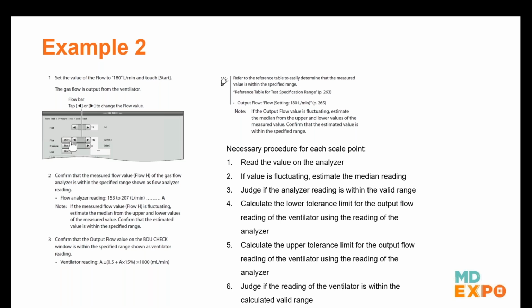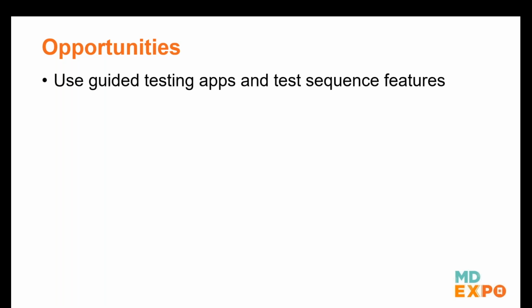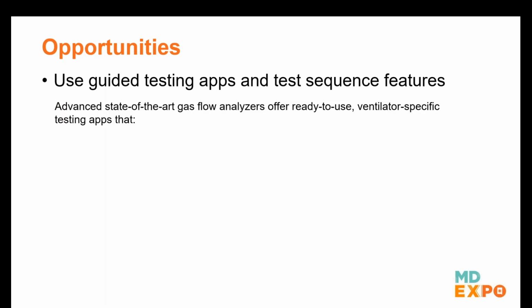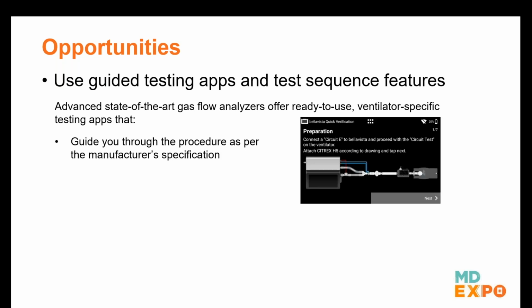So the last opportunity I want to talk about here is actually a feature that the latest gas flow analyzers on the market offer that not only resolves this challenge, but all the challenges we discussed so far. And it's to use guided testing apps or test sequence features. So these gas flow analyzers have built-in testing applications for specific ventilators. So what they do is they guide you through the performance verification of that specific ventilator.